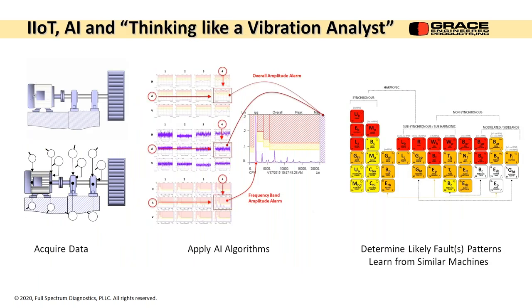This is kind of the flow chart. So I have acquiring data with my transducer up here. I can also acquire phase data, like we've mentioned. If all these transducer locations are linked together, I can get live phase analysis, which is fantastic. So we have overall vibration levels, we have time waveforms, we have spectrums that we can capture, right? Right now, we're doing little packets of overall levels, so we're getting the least diagnostic information. But if something changes and goes into alarm, that prompts us to take a spectrum, take a waveform. And we don't have to take it everywhere. We can target the location that the alarm came from. So once we have that, we can start using this type of logical sorting mechanism that will be able to tell us what the root cause of the problem is.